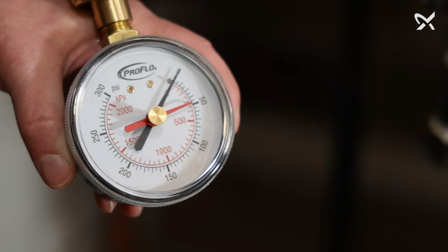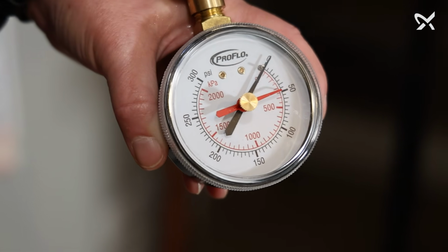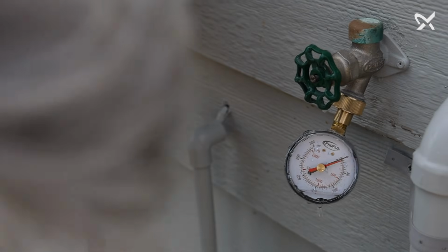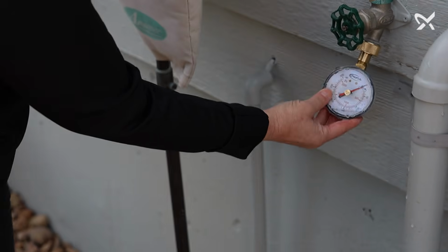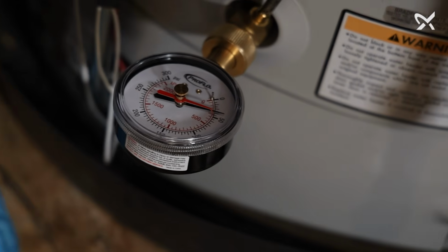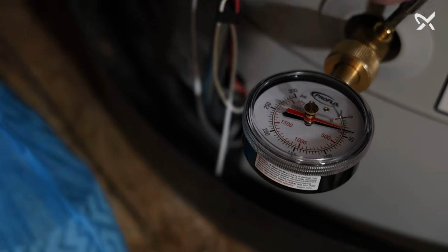Okay, so the next thing we're going to do is verify inlet and static pressure, and the best way to do that is with a red line gauge. You can attach this to an external fixture and let it run overnight. The gauge will actually move that needle, so if you have high pressure spikes in the middle of the night, the gauge will tell you, and you might need to put a pressure reducing valve on the system. The other thing is to test it at the boiler drain on the water heater. Make the attachment, and that's how you can find out what your internal static pressure is. We need that information because that's how we're going to establish our set point for the boost.